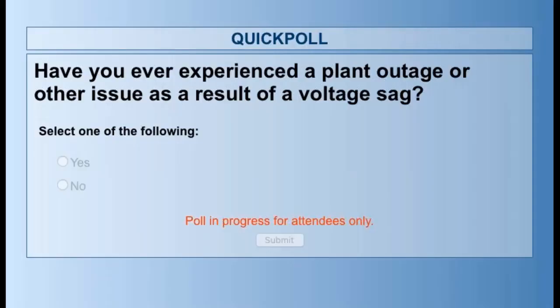So we look at power quality as three types of events. The first consideration is a chronic voltage problem, where you have an ongoing high or low voltage situation. The next would be voltage sags. These typically are quick, sometimes only 2 or 3 cycle events, but they are long enough in duration to cause issues with your piece of equipment, your process, your factory, whatever it may be. So the top two are issues that UST has products to address. The third event type is a complete interruption. We leave that for the UPS people. We do not have a solution for complete interruptions.